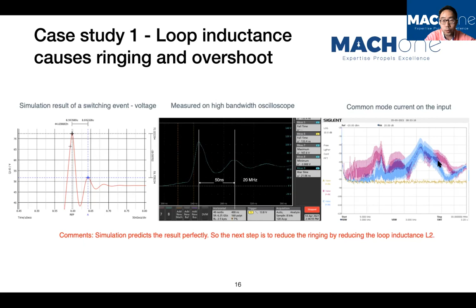Just to double check, as mentioned before, your time domain measurement has a relationship with your frequency domain measurement. So we put a current probe on the DC bus line and measured the common mode component. At 20 megahertz we've seen a big resonance. Altogether it makes perfect sense, and we know the long lead inductance is the problem - that's the noise source.